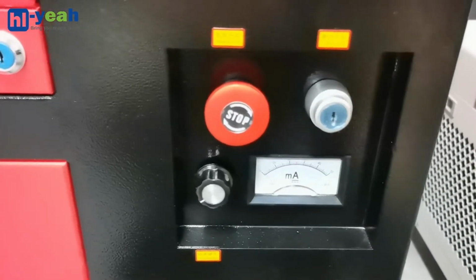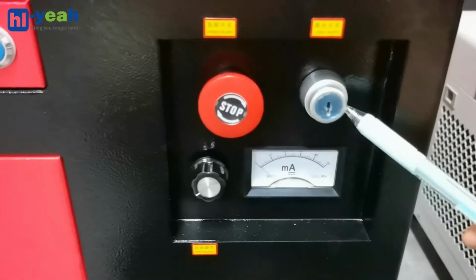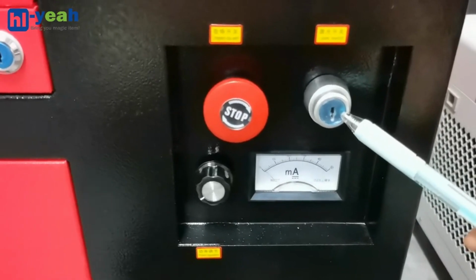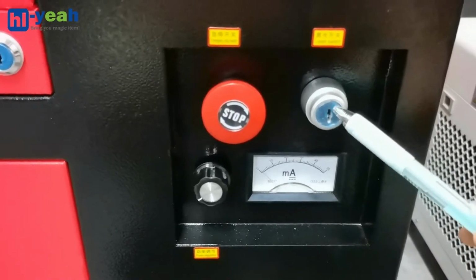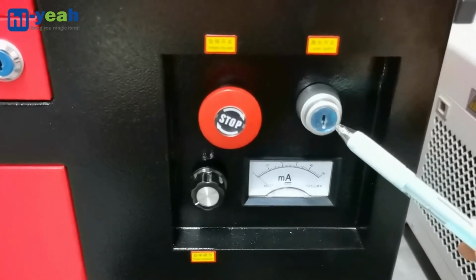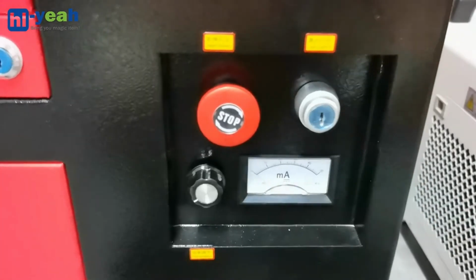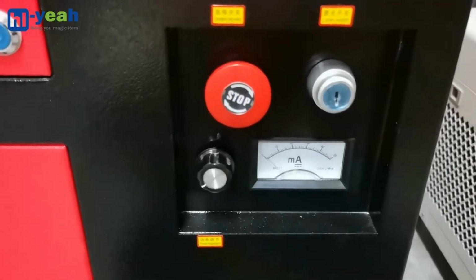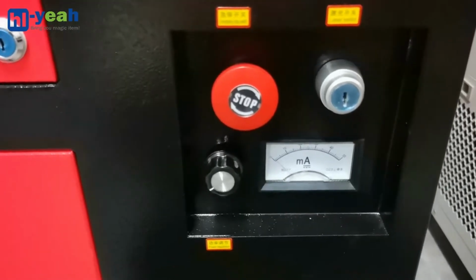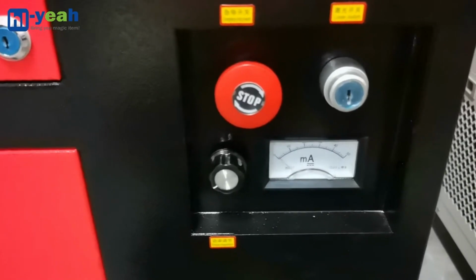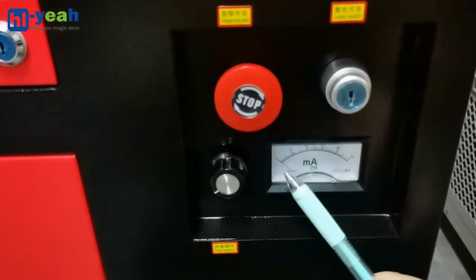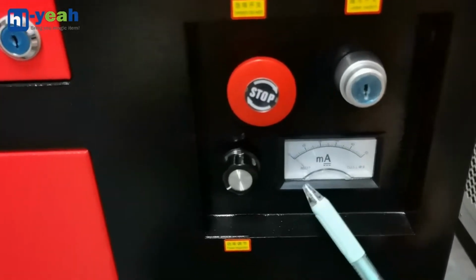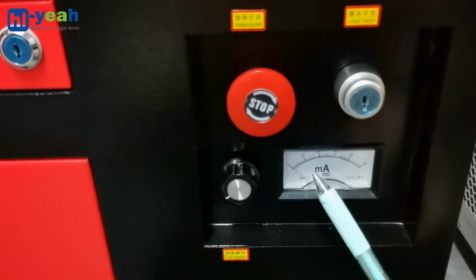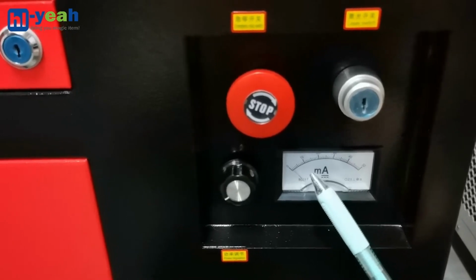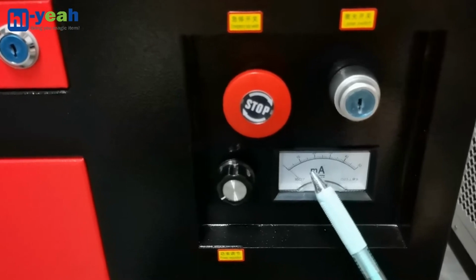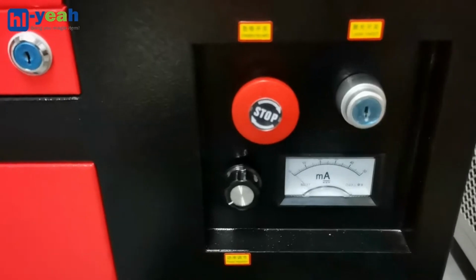The key button next to it is the laser switch. This controls the laser output. You need to turn it to the right to start the laser firing. Next, you will see the ampere meter. Once you have laser output, you will see the indicator vibrating. It's very useful. You can see the ampere output, and check if the laser output is normal or incorrect.